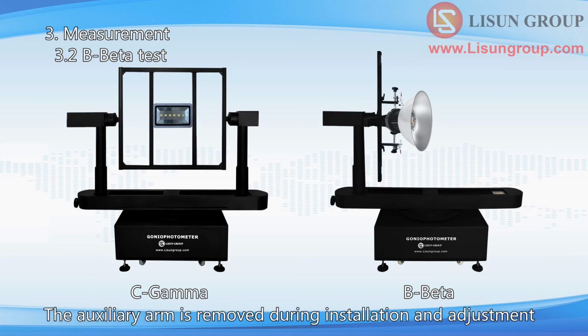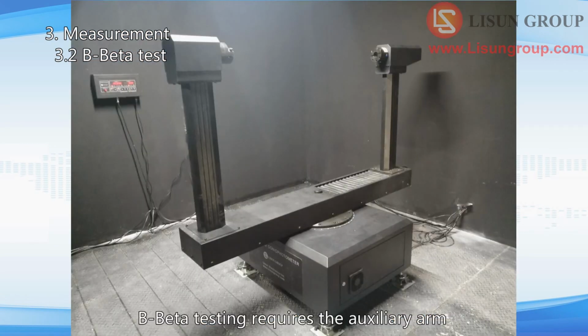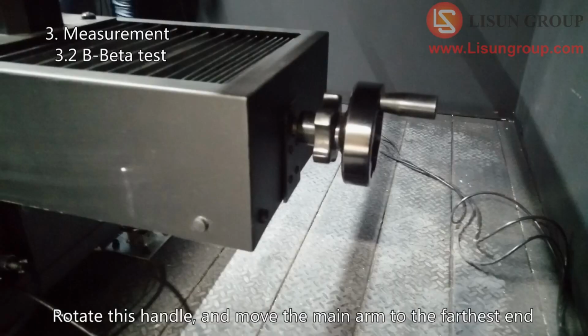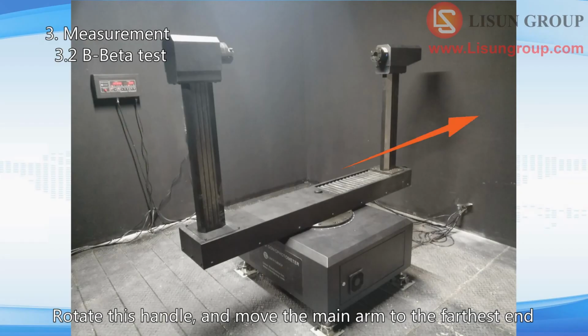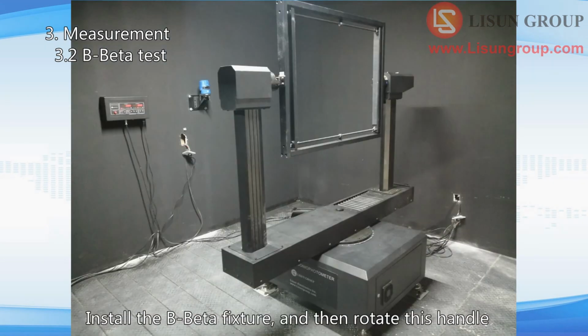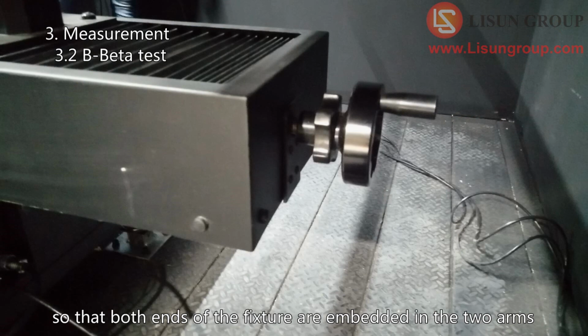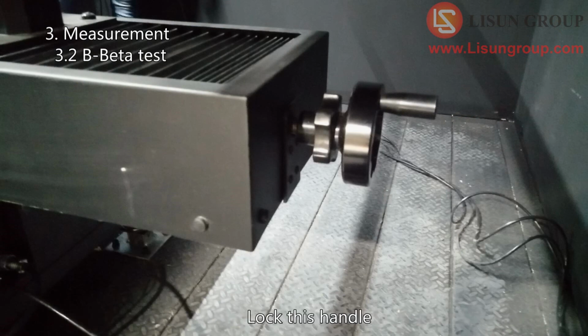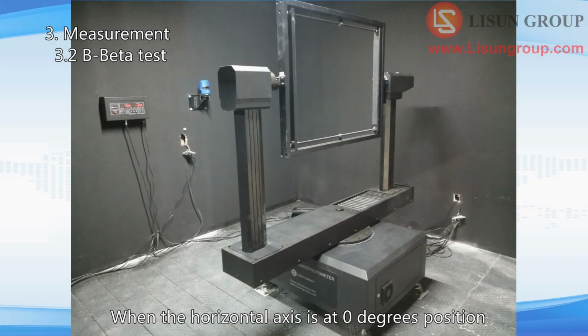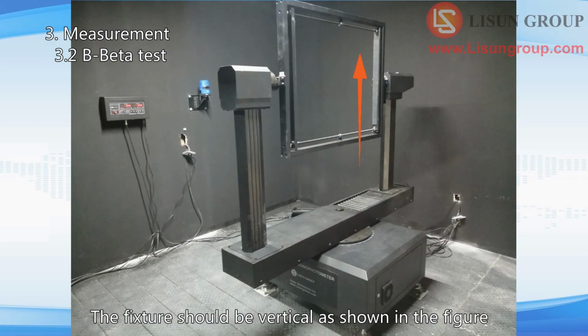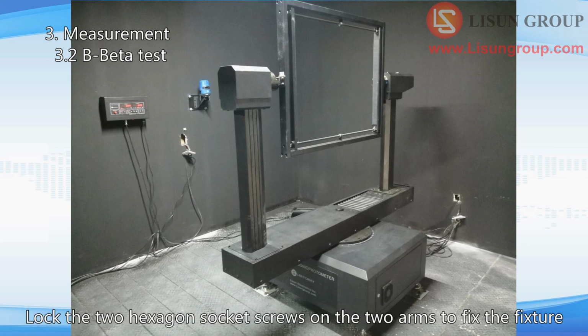The auxiliary arm is removed during installation and adjustment. B-beta testing requires the auxiliary arm. Rotate this handle, and move the main arm to the farthest end. Install the B-beta fixture, and then rotate this handle so that both ends of the fixture are embedded in the two arms. Lock this handle. When the horizontal axis is at 0° position, the fixture should be vertical as shown in the figure. Lock the two hexagon socket screws on the two arms to fix the fixture.